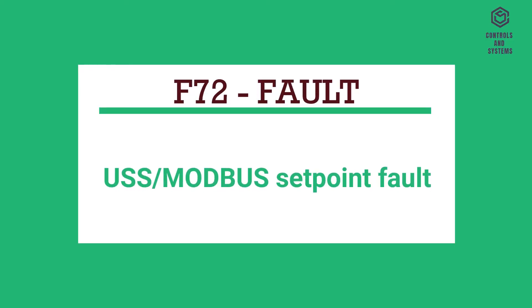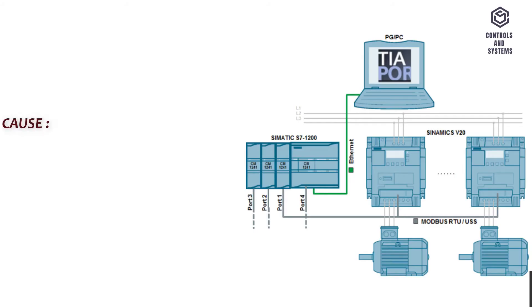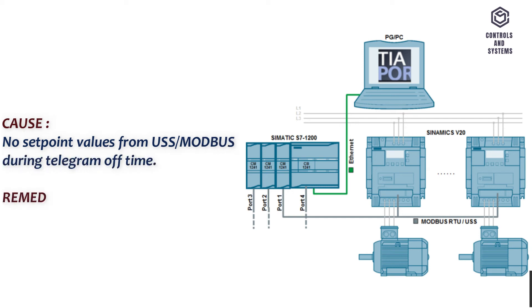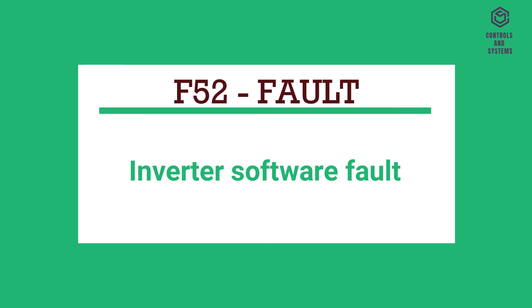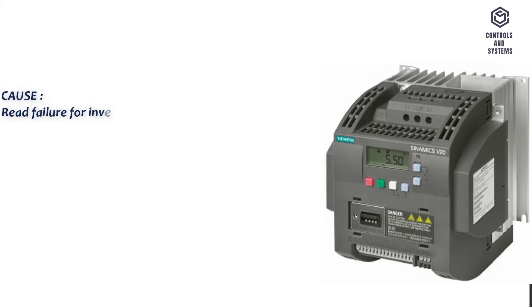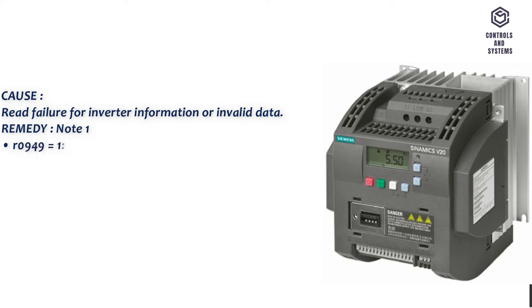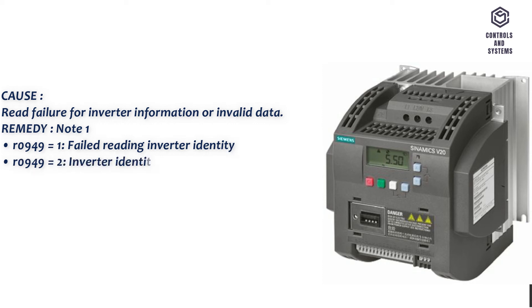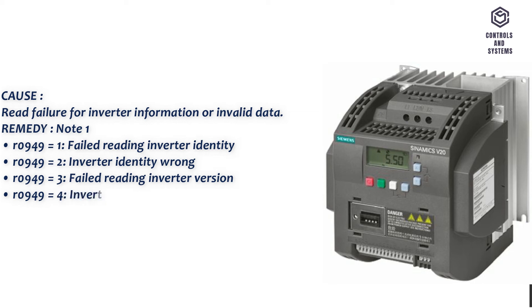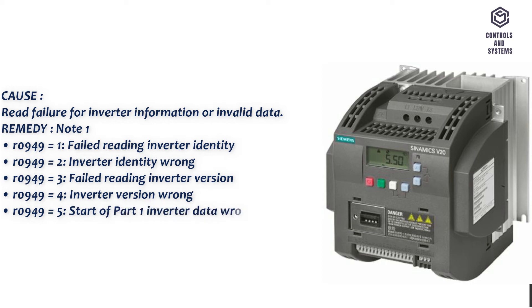F52 Fault: Inverter software fault. Cause: Read failure for inverter information or invalid data. Note 1: R0949 equals 1: failed reading inverter identity. R0949 equals 2: inverter identity wrong. R0949 equals 3: failed reading inverter version. R0949 equals 4: inverter version wrong. R0949 equals 5: start of part 1 inverter data wrong.